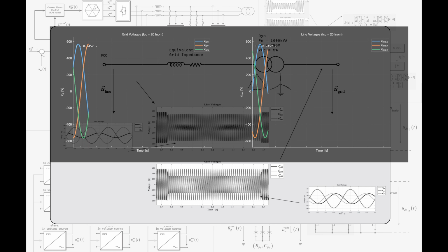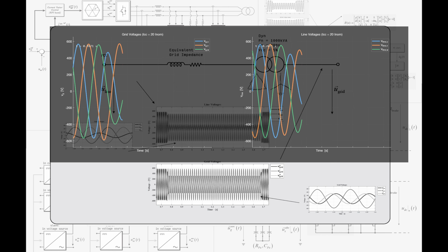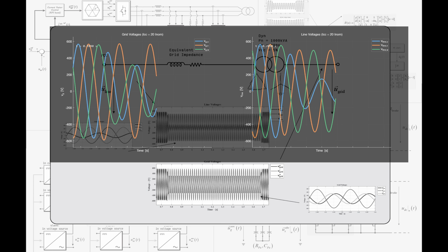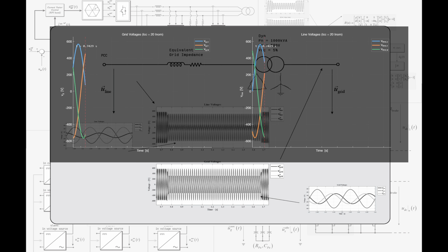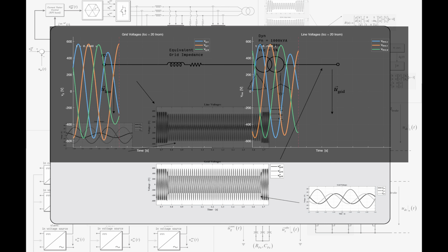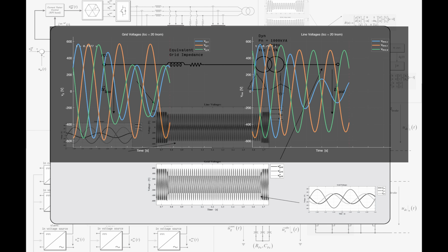As shown in the figure, the voltage dip upstream of the transformer originates from a single phase to ground fault. The effect of this fault, as seen downstream of the transformer, is also illustrated. The single-phase fault is converted into a two-phase fault. Nevertheless, this voltage dip represents one of the most critical scenarios with respect to reactive current compensation and DC link voltage stability. Indeed, an unsymmetrical voltage dip gives rise to a double-frequency power oscillation at the grid inverter interface, which adversely affects the overall control stability.